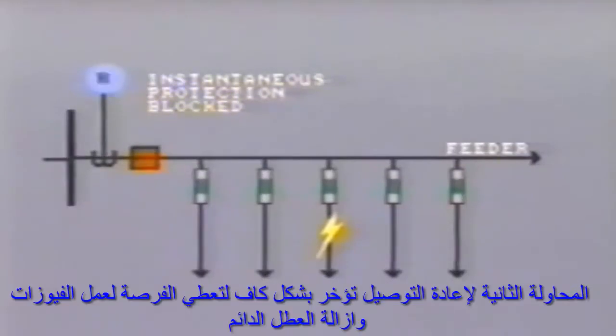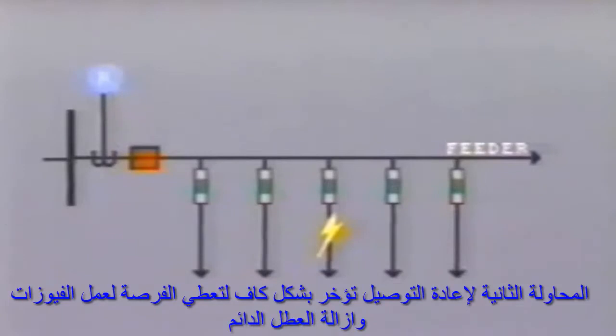On most feeders, there are a large number of fused taps supplying different customers. The protection scheme may be coordinated so that if a temporary fault occurs downstream of any fuse, the feeder breaker protection will operate first. It will instantaneously trip the breaker and then instantaneously reclose again. If the fault remains on, that is a permanent fault, the breaker will not trip the second time, as the instantaneous protection is now blocked. The second attempt at reclosing is delayed sufficiently for the local fuse to operate and clear the permanent fault.